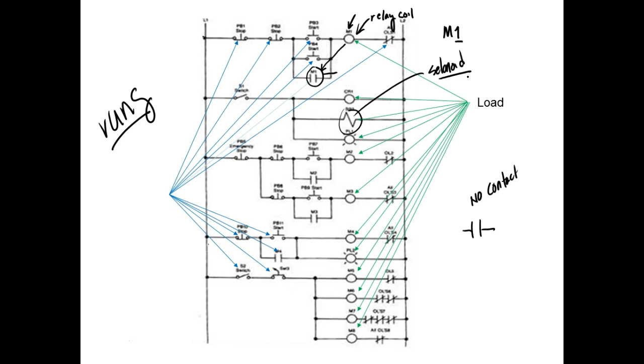So L1, and these are generic terms, and like I said, this gets people in trouble in motor controls. If we come over here and look at our disconnect, the big gray box, it's labeled L1, L2, L3. And those are 208 volts.